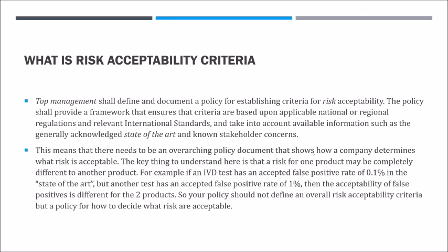That's absolutely fine as long as you define what each of those numbers means. So, for example, if 5 was unacceptable severity, you could define that as causing death, because if your state of the art says that your device is not supposed to cause death, and you look in the state of the art and no device has ever caused death, you know that the risk of causing death for your device is not acceptable, and hence it will be very high on the severity scale.